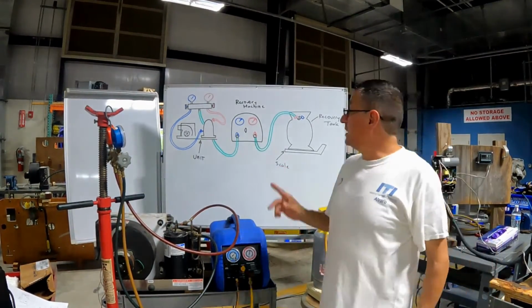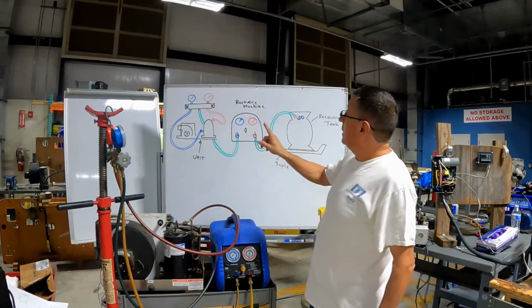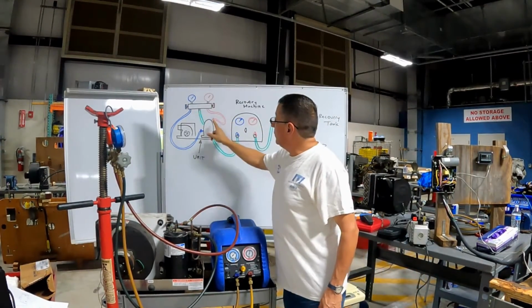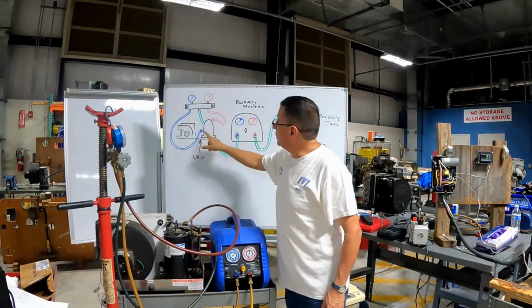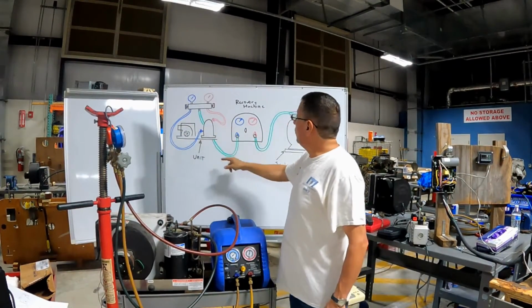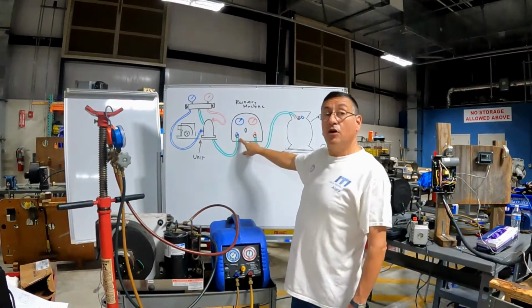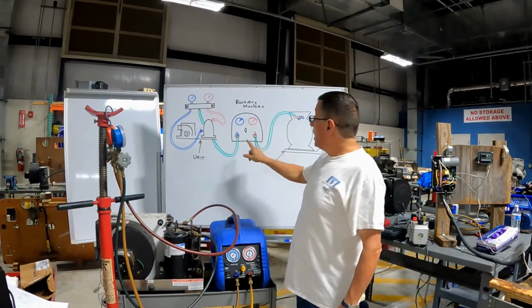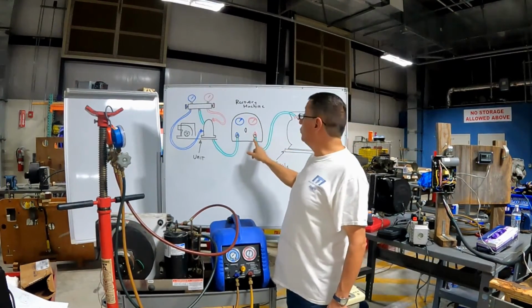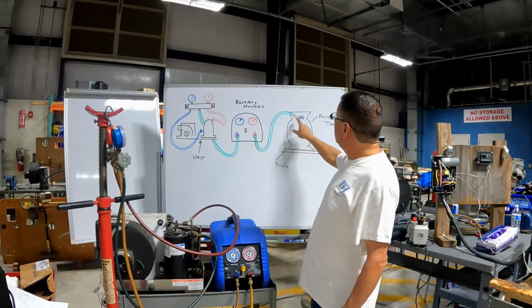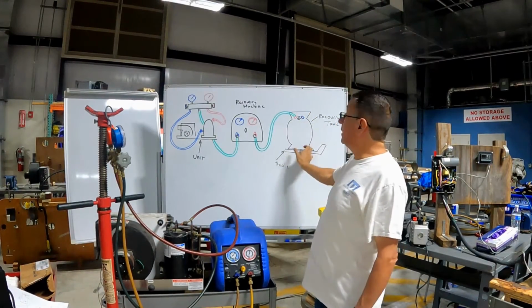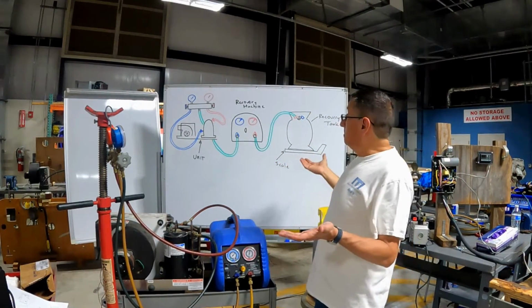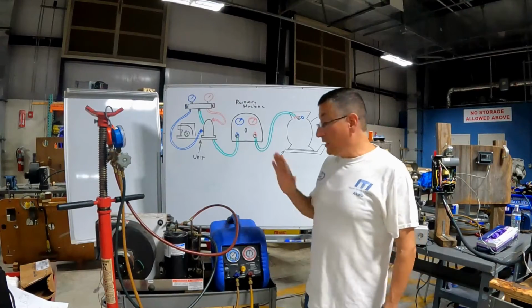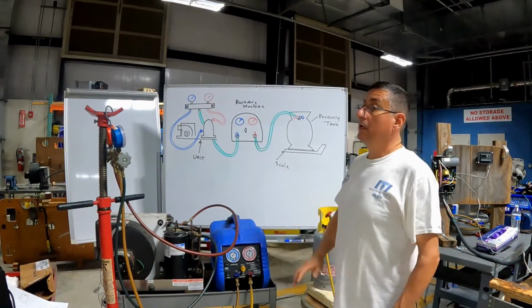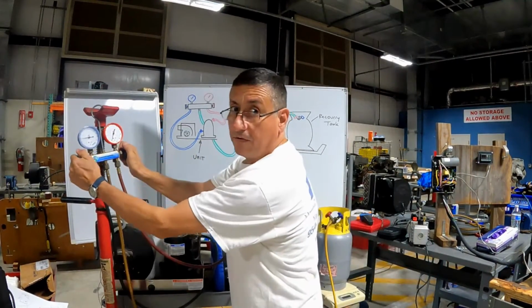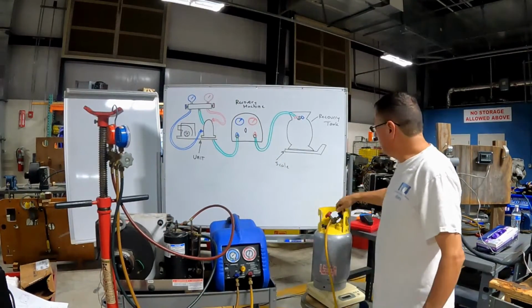Okay, right now the set is connected in this way. High pressure with high pressure of the compressor, low pressure with low pressure of the compressor. The middle one in the suction side of the equipment, and the additional hose in between the discharge and the liquid port of the container. That's simple. This equipment is off, the set of gauges are off, and the cylinders are off.